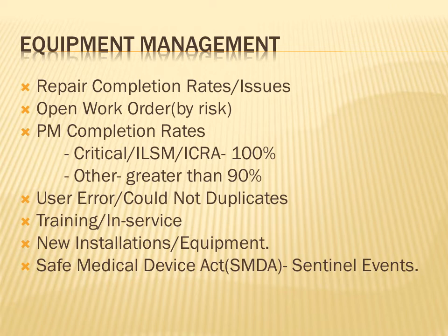a facilities perspective. Again, I mentioned Safe Medical Device Act. Again, that should be in every report, even if there's nothing that's happened. You have studied and learned and heard about sentinel events, again, when someone gets injured or dies in healthcare. Some people would say that near misses should also be included in sentinel events. That is not driven by language, by code. But near misses, obviously, if something else happened, it would have been a sentinel event. Some people do include near misses in their sentinel event reporting, but I think very few people do.